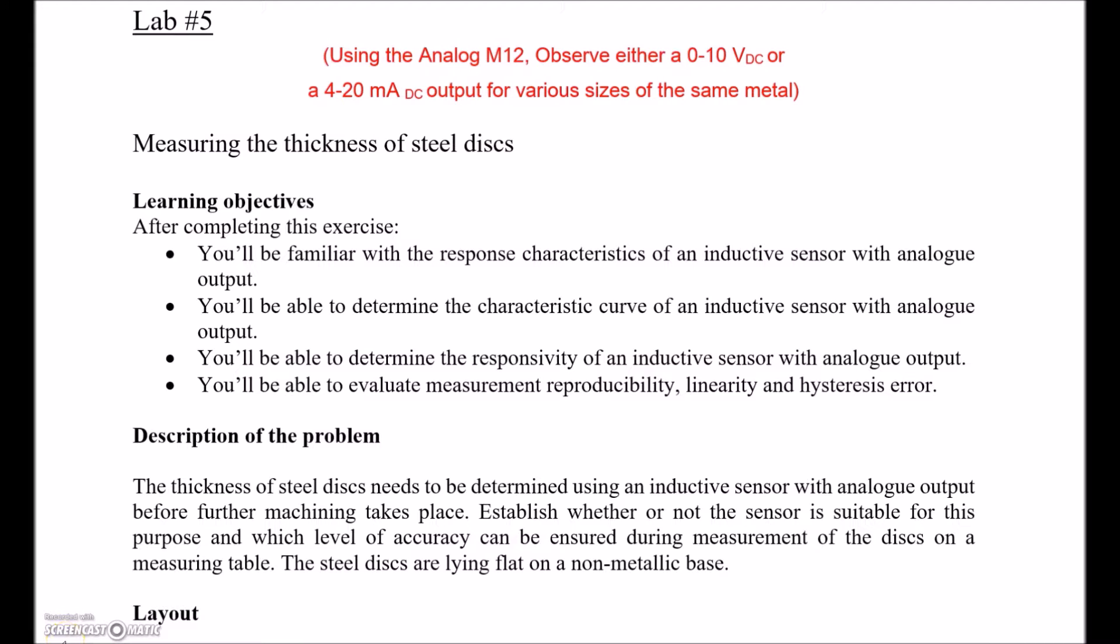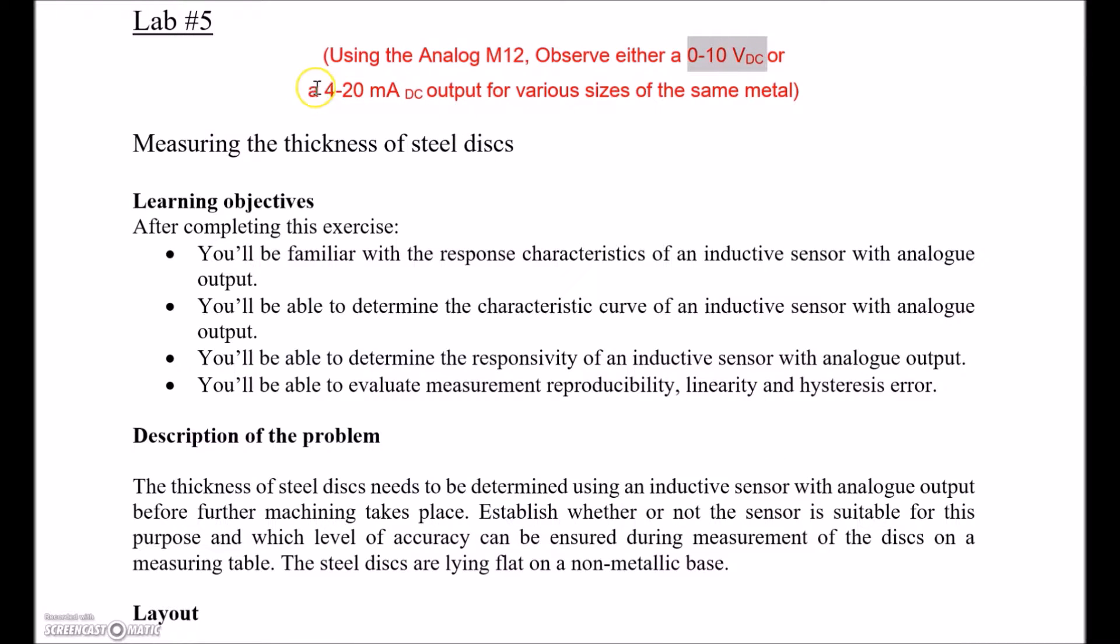Alright guys, number 5. This one is looking at an inductive sensor, but we're going to switch up when we're going to grab the analog M12. Looks exactly the same as the discrete output M12, but this one has threads all the way to the end, and it's going to provide us with either a 0-10 volt DC voltage out, or it's going to give us a 4-20 milliamp current out.